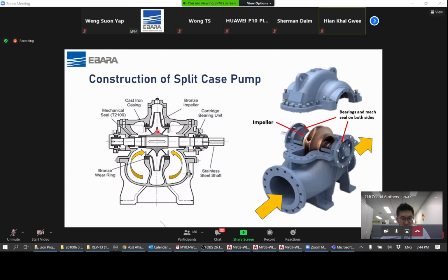So, as I did mention to you, in such a design, it creates a much more balanced hydraulic as well as dynamic forces within the pump. And also because of that, usually split case pumps have much higher efficiency compared to, let's say, an end suction pump for the same flow rate and head.